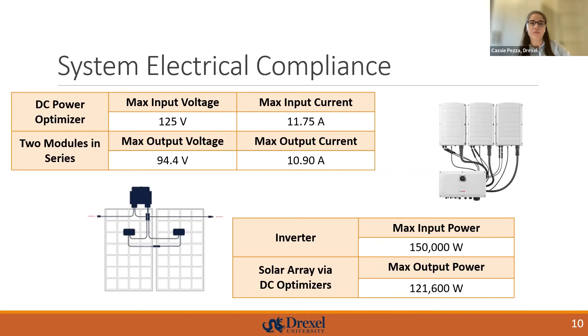The inverters are arranged in such a way to limit the DC wiring between the optimizers and the inverters. As shown in the slide, the maximum output of each panel series layout remains below the maximum input allowed for the DC optimizers and the inverters. Additionally, the connecting wire will be gauged accordingly to comply with the NEC standard, limiting voltage drop below 5% overall and 3% in each branch.